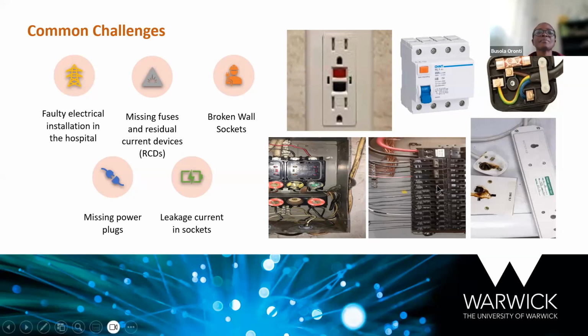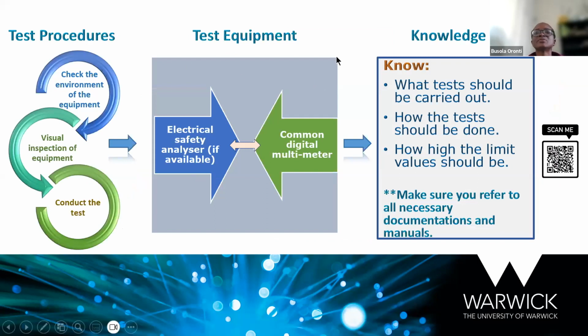So when we are talking about the safety of medical devices, we need to follow test procedures. The first thing to do is to check the environment of the equipment, especially for low-income countries. Don't go to the equipment first. Check the environment. Check what's wrong with it, like we said before. Check whether you have broken sockets and stuff like that. Maybe some fuses are not where they should be. Those are the things you should check first. Then secondly, you can go to do a visual inspection of your equipment. And then finally you conduct the test.